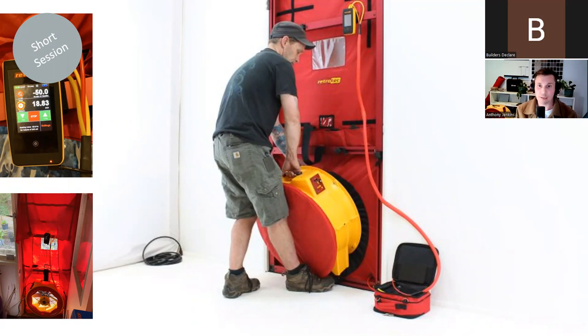All exterior openings such as doors and windows need to be closed, and all internal openings need to remain open while testing. There are also safety measures to be aware of, such as any wood or gas heating appliances needing to be extinguished, including the pilot. There is a standard we test to — the Australian/New Zealand ISO standard AS/NZS ISO 9972 — which states we pressurise the home to 50 pascals. The controller can then tell us how many times the air for the entire volume of the home is being changed over a one-hour interval, typically abbreviated as ACH at 50pa.